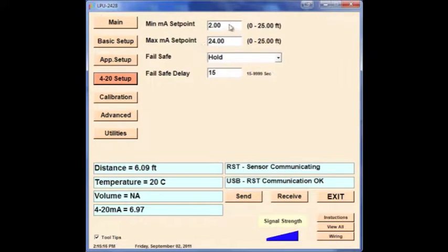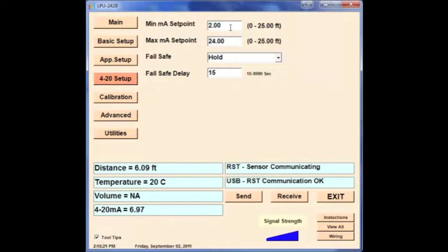Next click the 4-20 Setup button in the left menu to set your minimum milliamp setpoint. This is the 4 milliamp setting, and the maximum milliamp setpoint. This is the 20 milliamp setting.